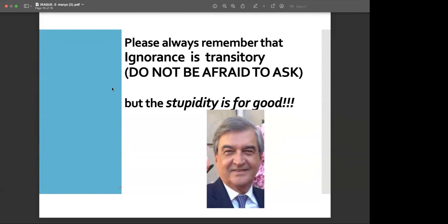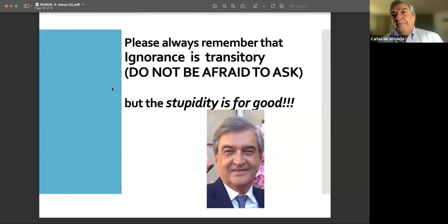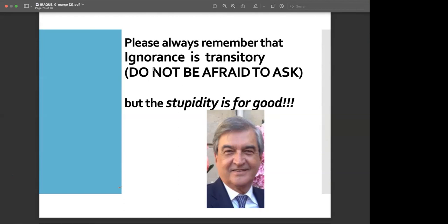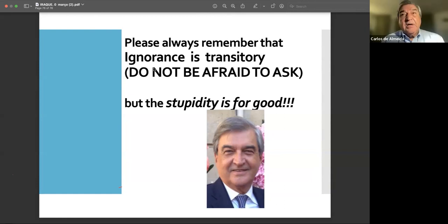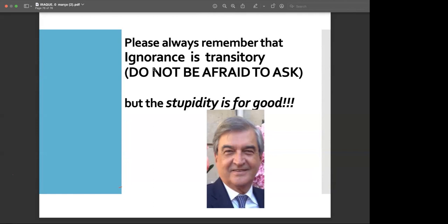Yeah, first of all, did you take a reading before you sent the chamber and after it came back, just to make sure there was not only a change in the N_DW but also a change in the chamber response? Did you do that? Yes, we do that. Okay. How long was it between the two calibrations? About 3 months, but we had been working with this ion chamber for 1.5 years.